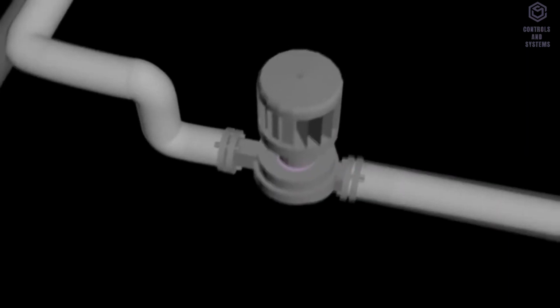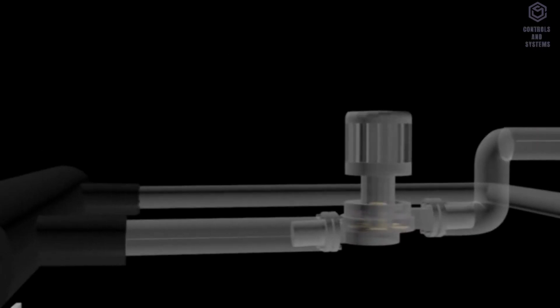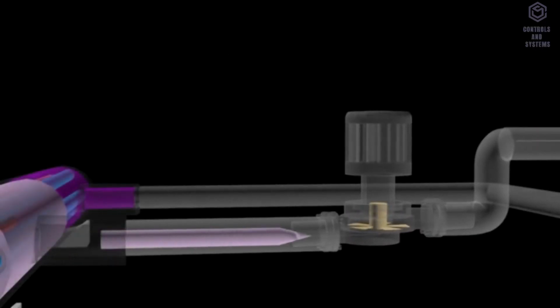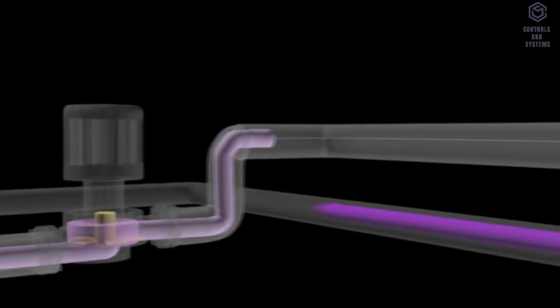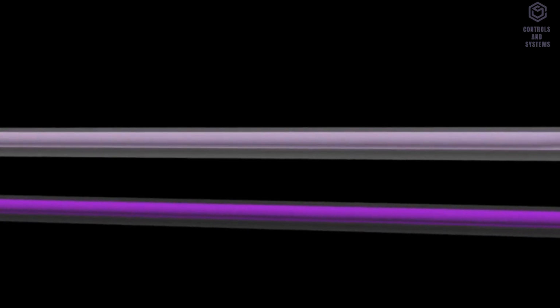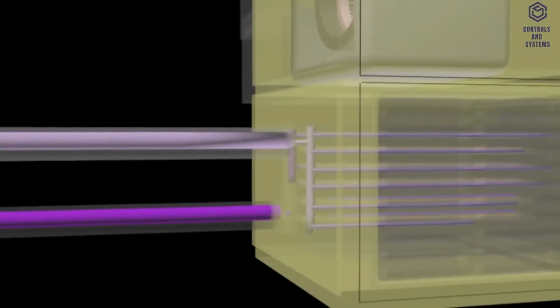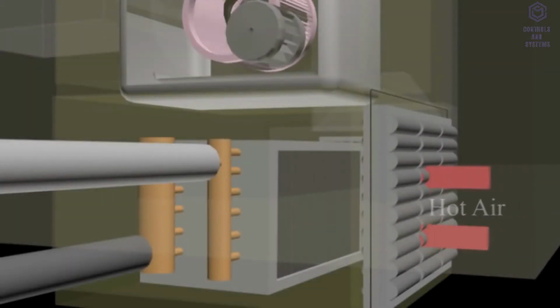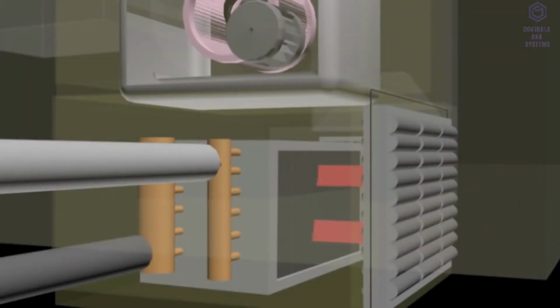Chilled water produced in the evaporator flows into the air handling unit through the pipeline which is marked with dark blue color. This chilled water is known as chilled water supply. In the air handling unit, chilled water will pass through the cooling coil. In the cooling coil, the hot air goes through the coil and turns into cold air due to the heat transfer to the chilled water.